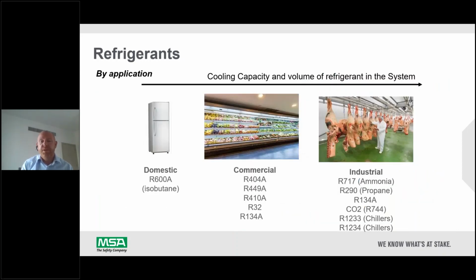The type of refrigerant used actually depends on the application. So at home in your refrigerators, you could have isobutane or R600A, which is flammable, but it's used in very small quantities, and it's an extremely efficient gas. In large commercial refrigeration, large chilling industries, chillers, they still use a lot of HFCs. And then in industrial food processing, they mostly use ammonia and carbon dioxide now, and then the large district cooling plants, which we see in the Middle East here, they use a lot of R1233 and R1234.